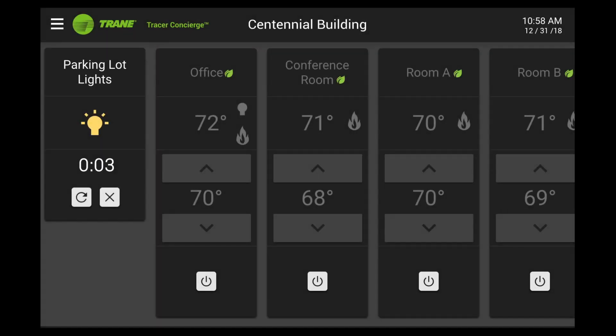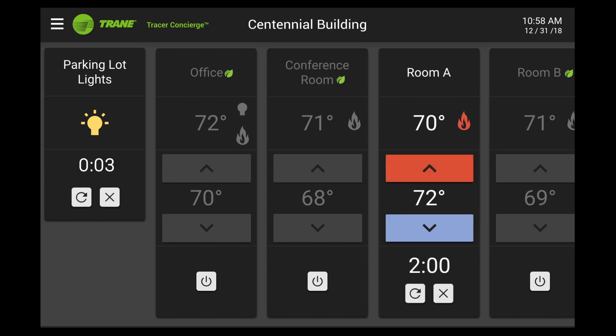HVAC and lighting can be temporarily enabled without editing the schedule. After-hours, this symbol will appear for the zones on the main screen. Pressing this button enables the HVAC. Lighting can be controlled in a similar fashion or in conjunction with the HVAC, depending on how the system is set up. These overrides are in effect for two hours. Tap the reset button to reset the override for another two hours.